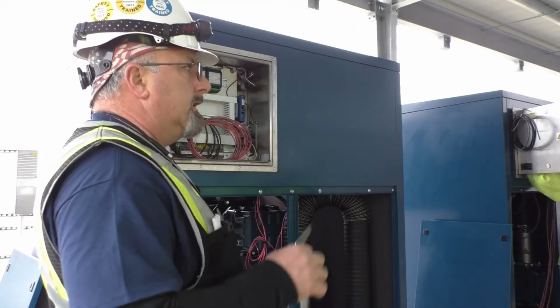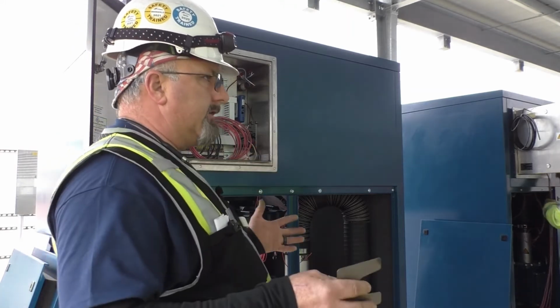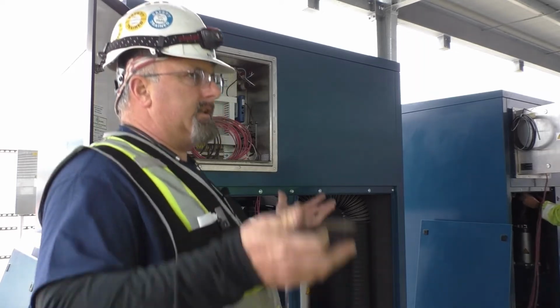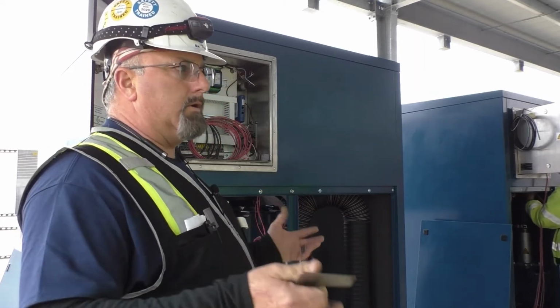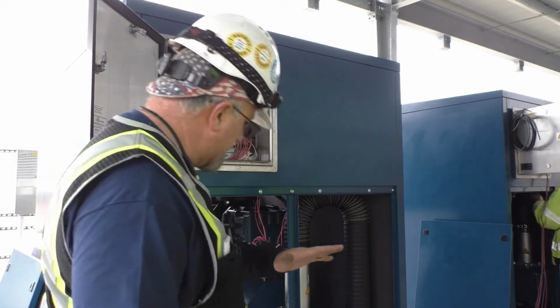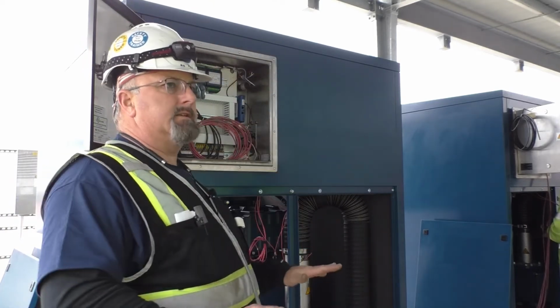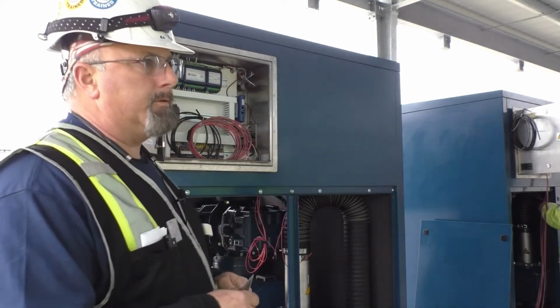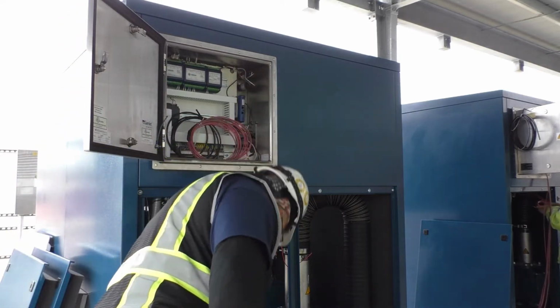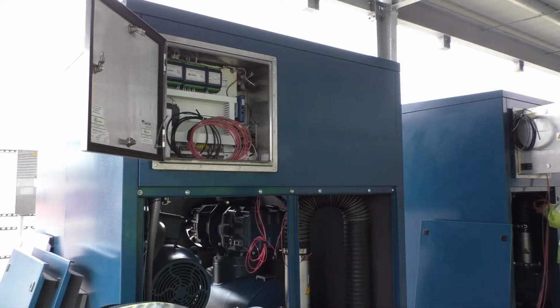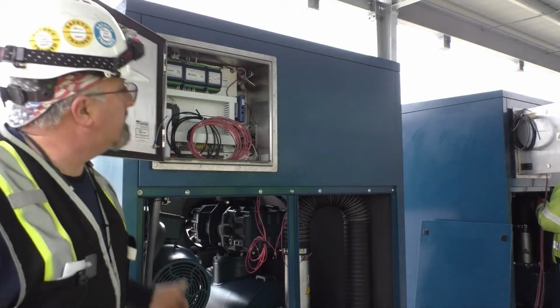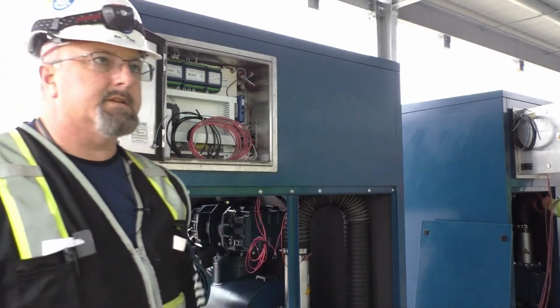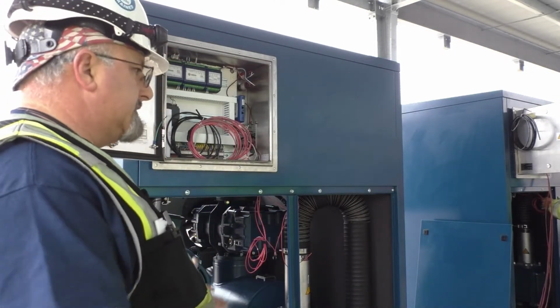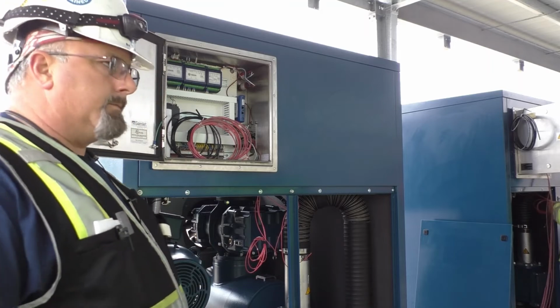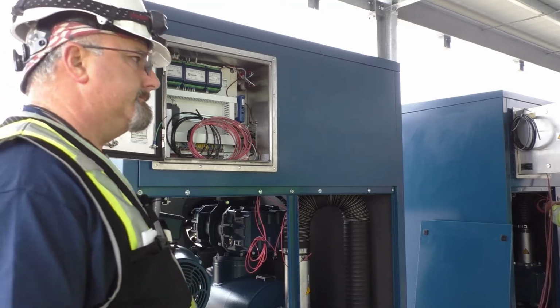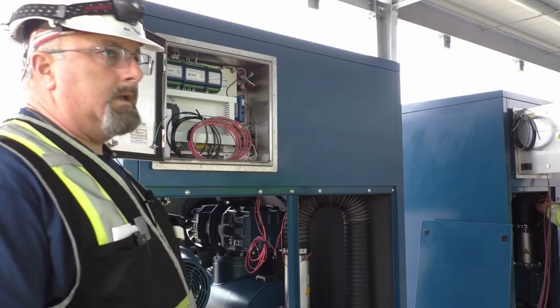The cabinets are structurally sound, but they're not designed to lift that entire weight of the blower at a single point. They're designed for that entire base to be sitting on the foundation for appropriate support. So for leveling, loosen this bolt, lift the frame up, and adjust as needed. Unless you have an issue with the slab, you'll probably never have to level. Any questions?